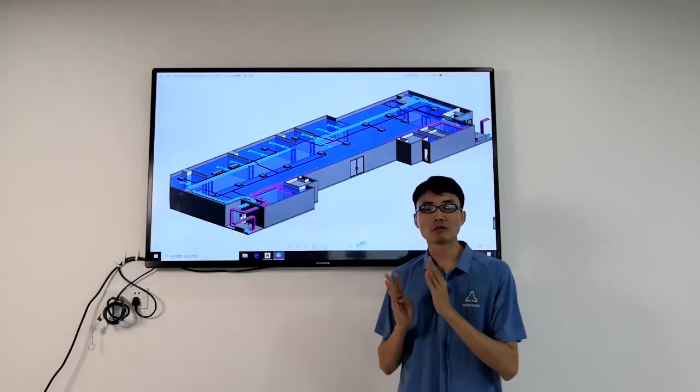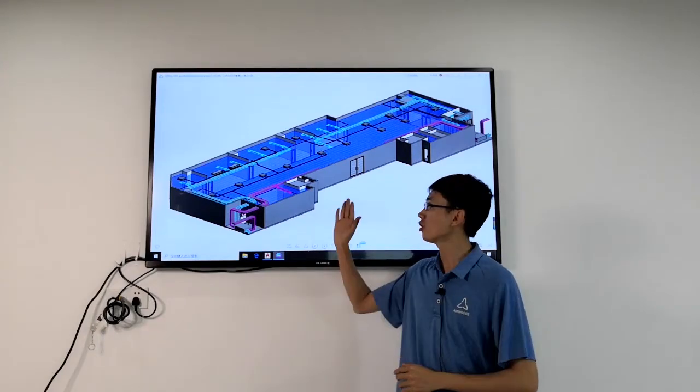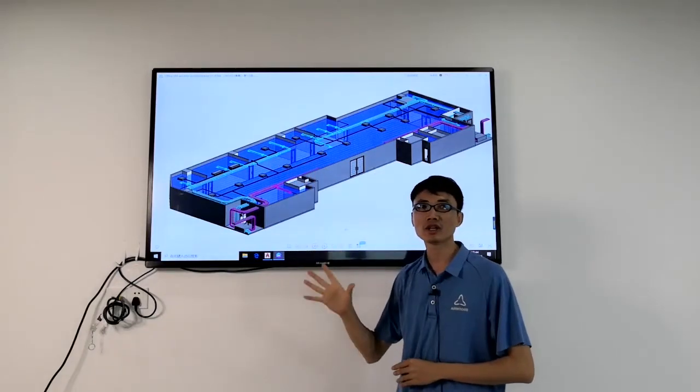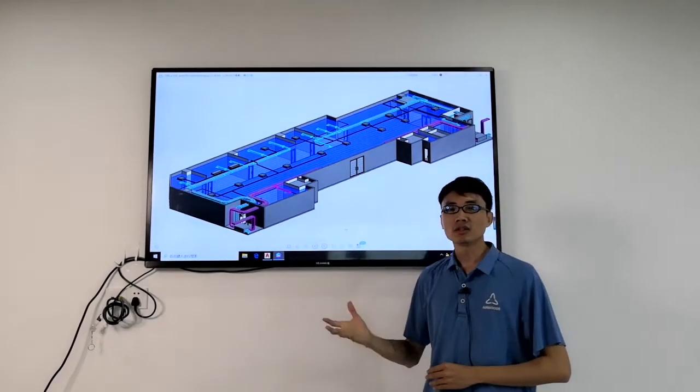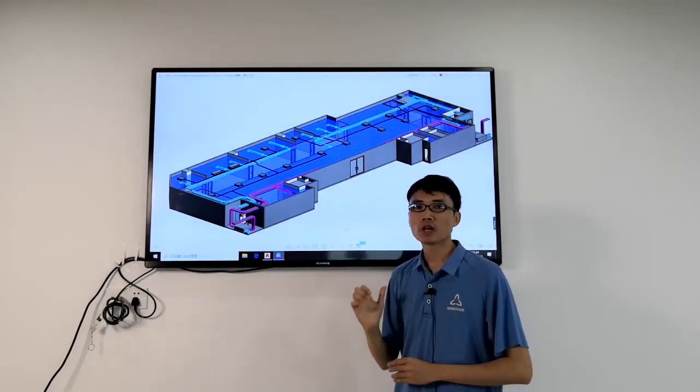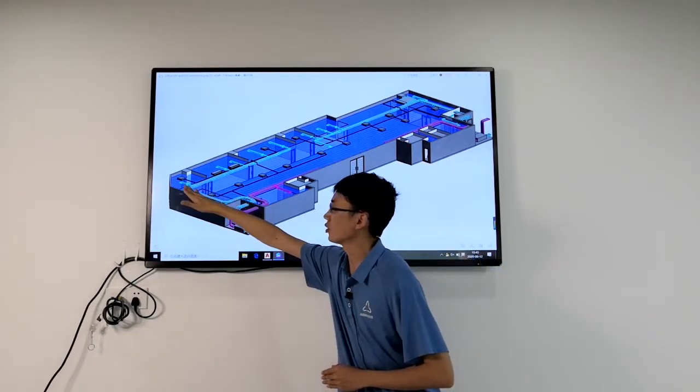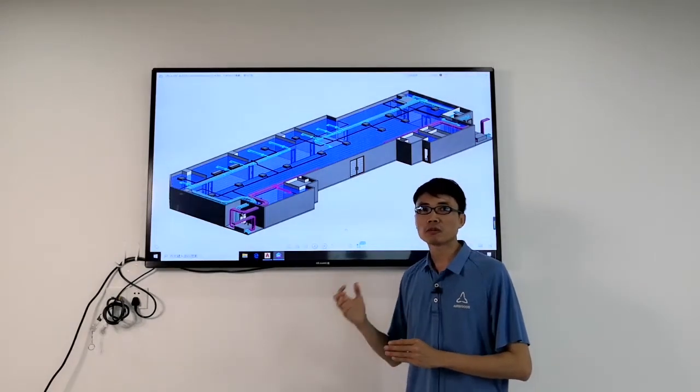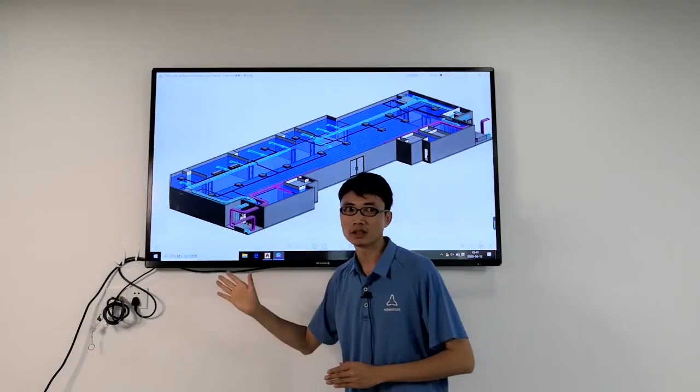The second point is the variable speed fan control. In each of the room, we would set a fresh air damper here. The ERV will regulate its fan speed according to the feedback signal from the damper, so the fan's power can be reduced accordingly when the room is not occupied.